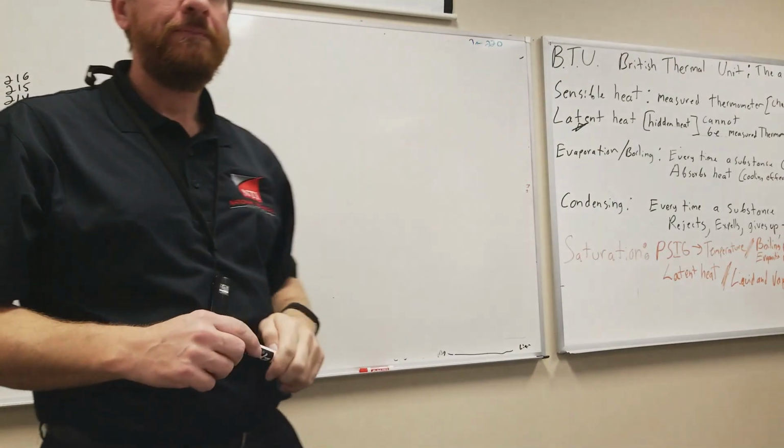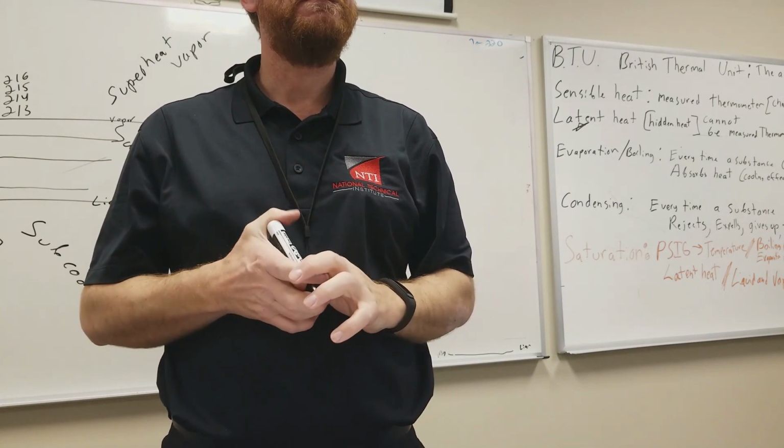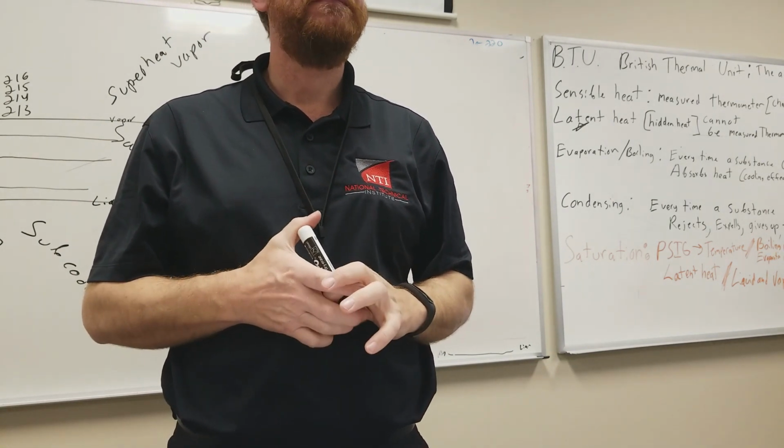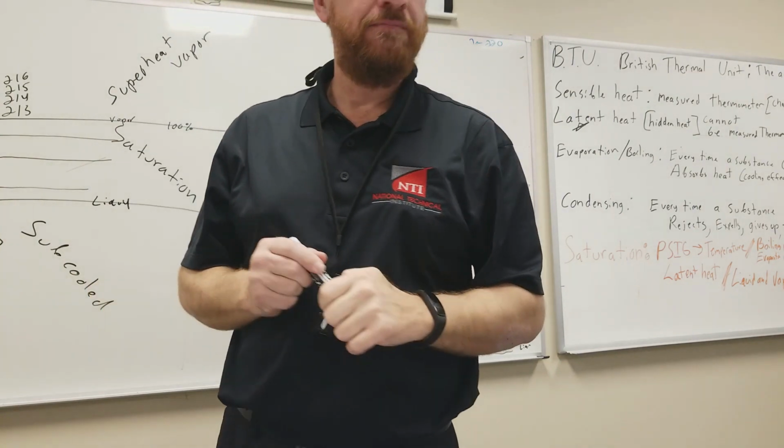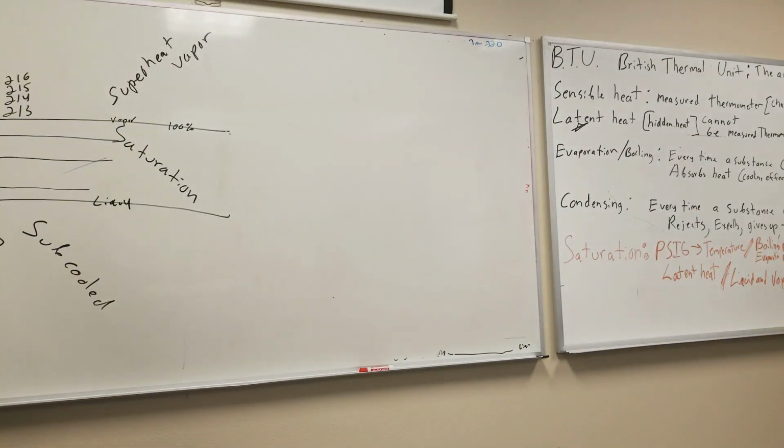Right now we're using water as an example to talk about the state, but what about inside the system? Since the compressor is adjusting the pressure inside... It is, but I can do the same thing with water. If I raise the pressure of water, what happens to my saturation temperature? It goes up. So if I put this in a pressure cooker and change this to being, say, 300 degrees Fahrenheit, my saturation changed with what? Pressure. So now what would I be here? Saturation. How much of this is vapor? We don't know. We can't measure it.